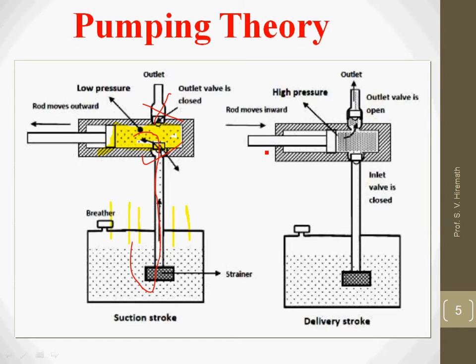And whenever we make the forward movement, in that case this check valve is going to be in a closed condition and this valve will open automatically because of the pressure difference. I don't have any path for this hydraulic fluid to move further, so the only option is the check valve, the ball will come out of the socket, so that I will be getting the flow through the outlet line.